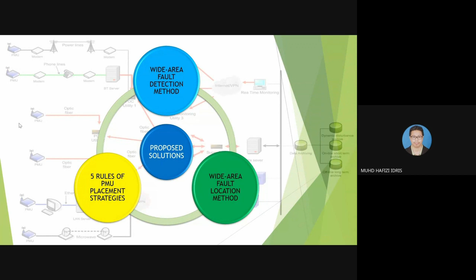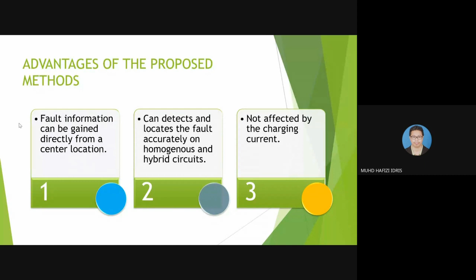Advantages of the proposed method: by using the proposed method, the fault information can be gained directly from a central location without the utility workers having to go to the substation to extract the fault information. The method also can detect and locate faults on homogeneous and hybrid circuits which have a combination of cable and overhead line. And the proposed method is not affected by the charging current of long lines.